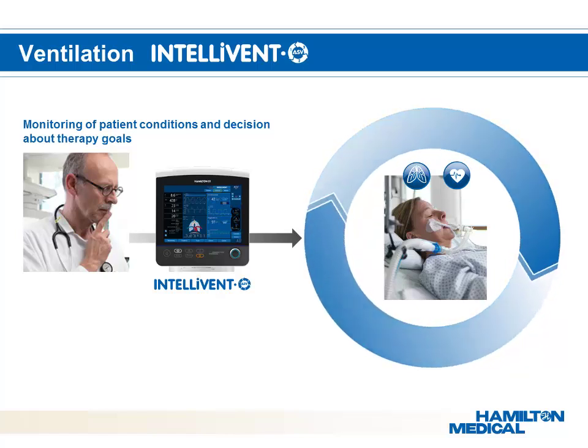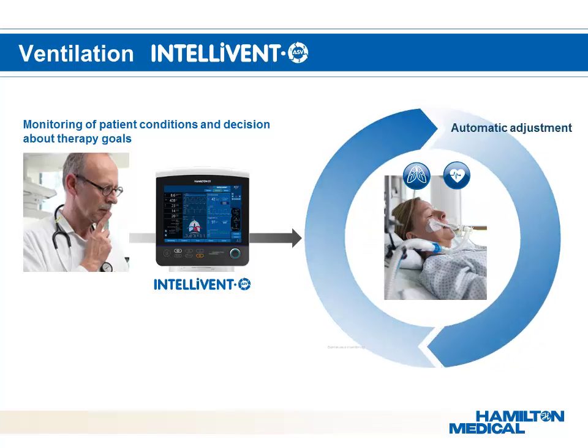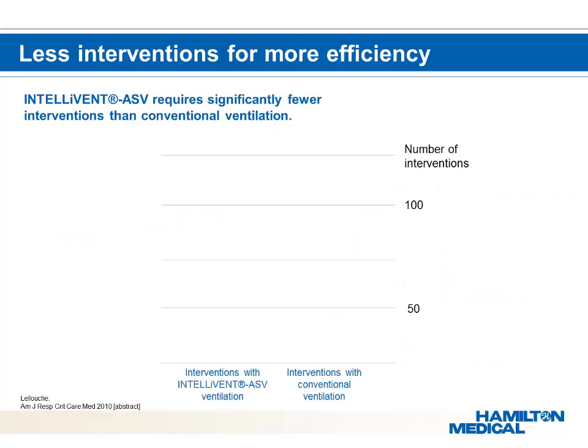The clinician observes and decides the patient's therapy goals. INTELLiVENT-ASV then automatically and continuously assesses the physiological status of the patient — measuring lung mechanics, FiO2, and ETCO2 — and applies the ideal and optimal ventilation and oxygenation, so the patient gets the optimal tidal volume, respiratory rate, pressure, FiO2, and PEEP.